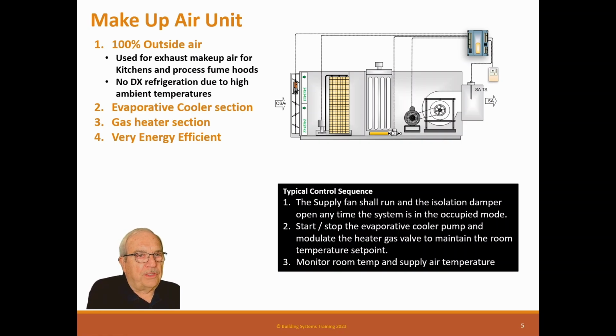The supply fan shall run and the isolation damper open anytime the system is in the occupied mode. Start and stop the evaporator cooler pump and modulate the heater gas valve to maintain room temperature set point. Monitor the room temperature and the supply air temperature.